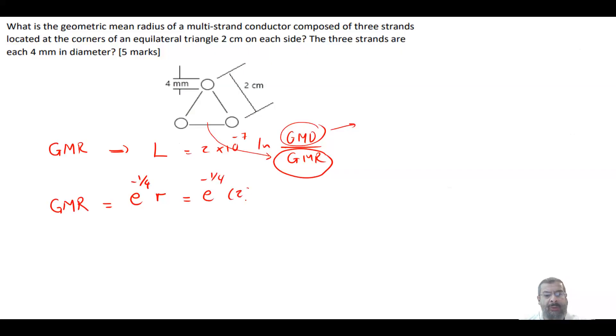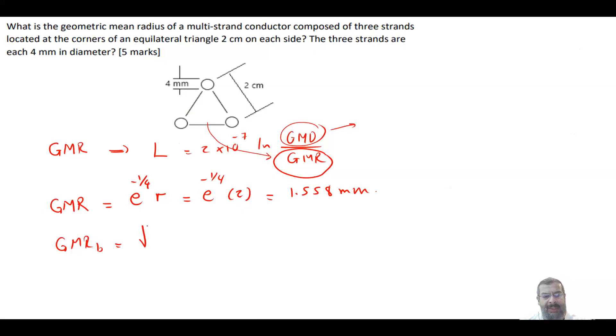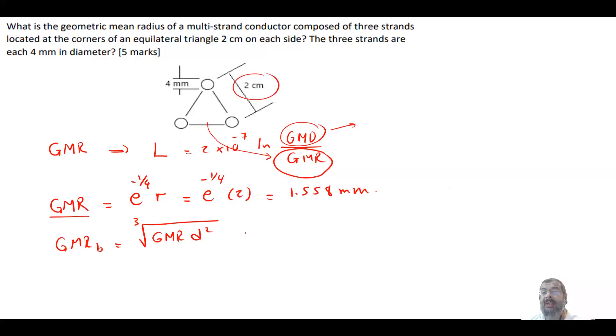So the single-conductor GMR equals e^(−1/4) × 2 mm, giving 1.558 mm. Then for the bundle conductor, the GMR is the cube root of (GMR_single × d²), where d is the distance between conductors in the bundle. This equals the cube root of (1.558 × 20²), giving a total bundle GMR of 8.54 mm.